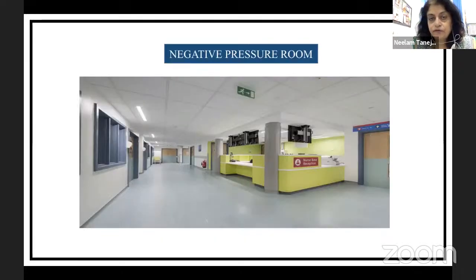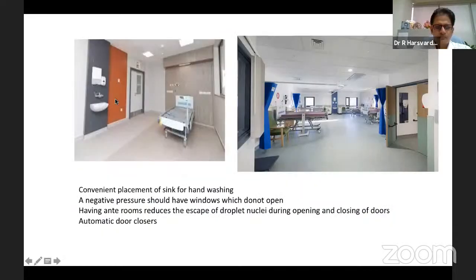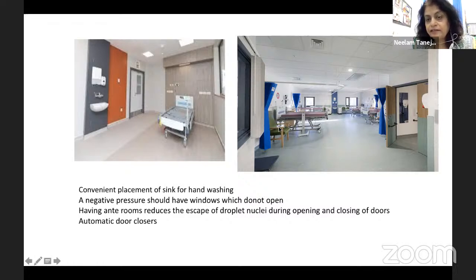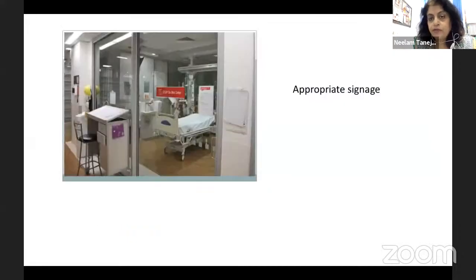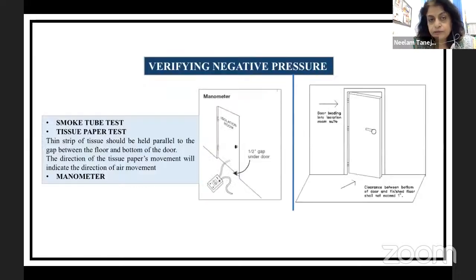This is a picture of a very nice negative pressure room developed at a UK hospital. Here these pressure isolation rooms are at the end, and this is a nurse space reception. You should have convenient placement of sinks for hand washing. When you're designing, this is a cohort isolation, negative isolation room. There should be windows so that the patient can see outside, but they should not open. Having an ante-room reduces the escape of droplet nuclei during opening and closing of the doors, and automatic door closers should be installed. There should be appropriate signage on the doors.